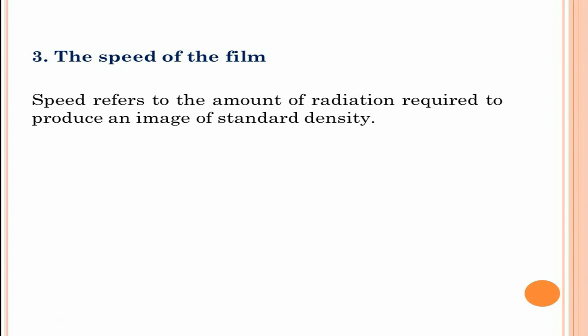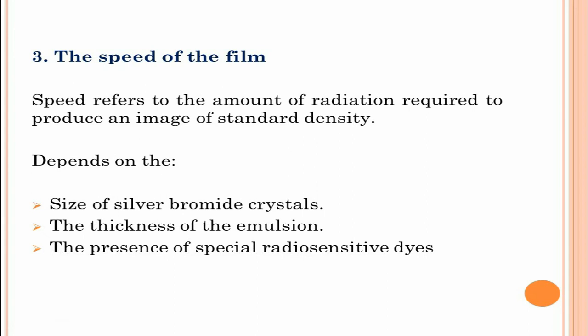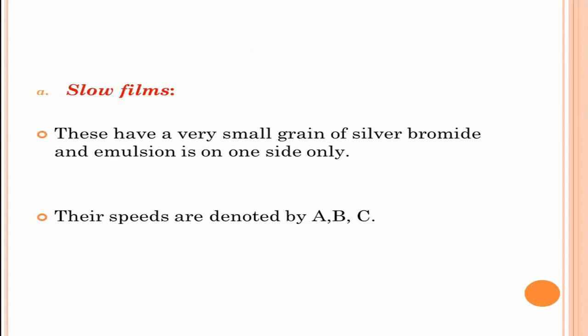Next classification is based on film speed. Speed refers to the amount of radiation required to produce an image of standard density. Higher film speed means less exposure is required compared to slow-speed films to form a similar image of same contrast and density. Film speed depends on factors such as size of silver bromide crystals, thickness of emulsion, and presence of special radiosensitive dyes. Based on speed, they can be classified into slow films and fast films. Slow films have very small grains of silver bromide and emulsion on one side only. They give better definition but exposure required is more and are not routinely used. An alphabetical classification is used to identify film speed, denoted by A, B and C.